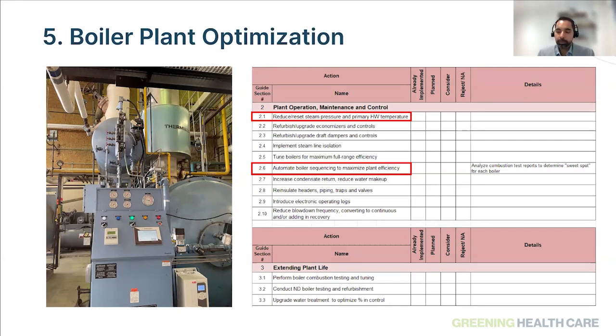Another thing we notice with the heating plant is that sometimes they are only connected to the BAS for a few functionalities, so it's always a good idea to check with the controls contractor whether your boilers are fully connected and automated and that the staging is done correctly. If the staging is not done correctly, what we're seeing is that 2 or 3 boilers come in at the same time when the load is not there, which creates a purge cycle and an unnecessary waste of energy from turning these boilers on and off. So again, automate this through your building automation system, ensuring that you have the right scheduling and right loading of these boilers based on the outside air conditions.